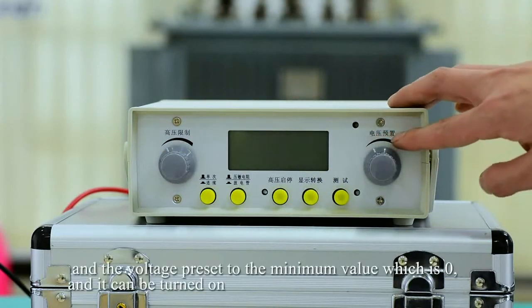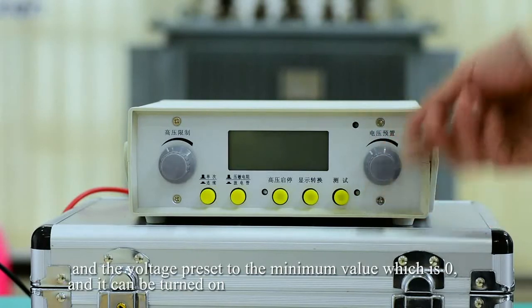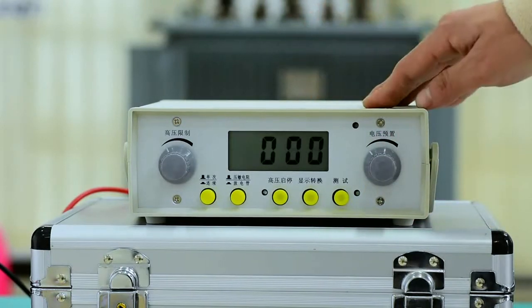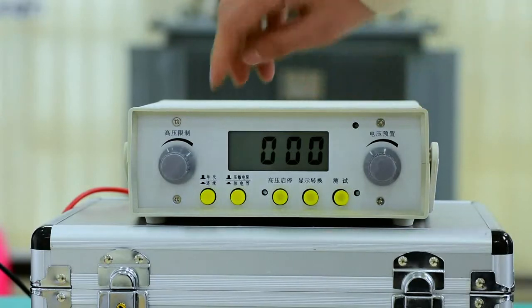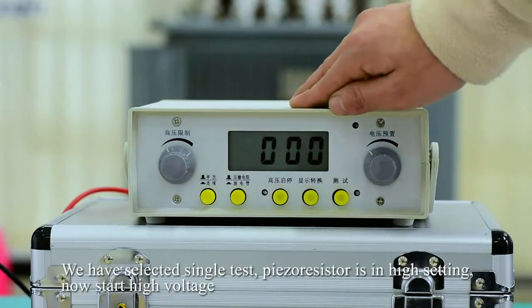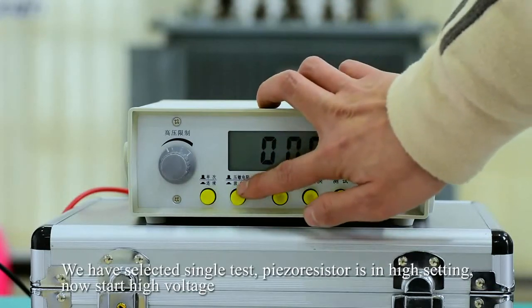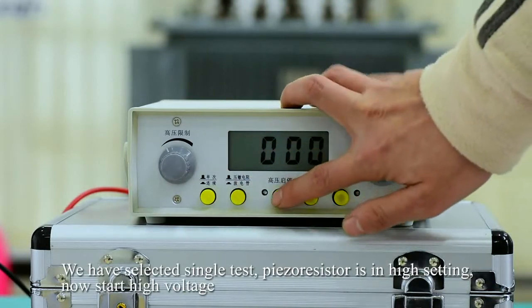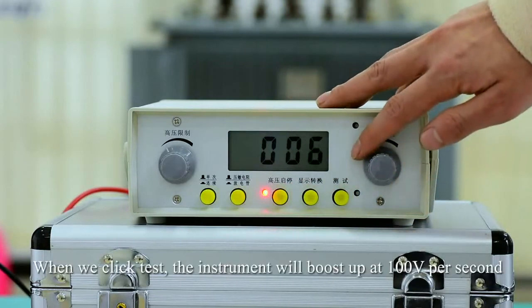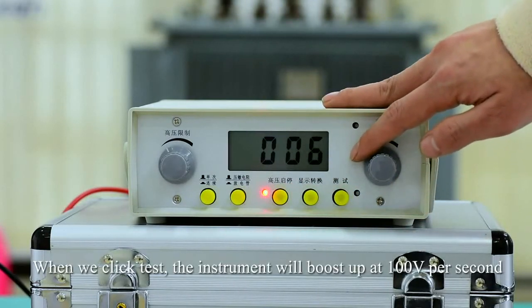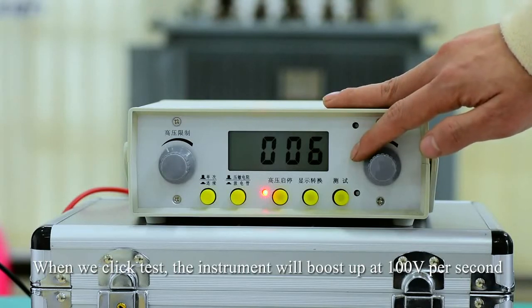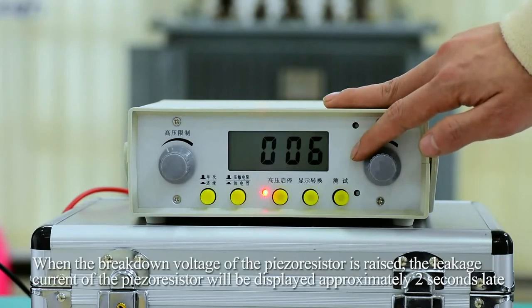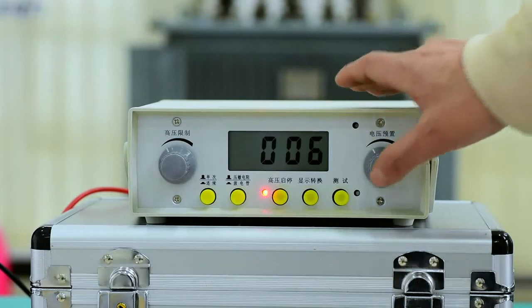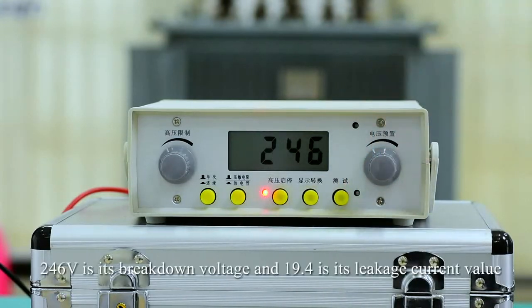And the voltage preset to the minimum value, which is 0, and it can be turned on. We have selected single test. The piezoresistor is in the high setting. Now start high voltage. When we click test, the instrument will boost up at 100 volts per second. When the breakdown voltage of the resistor is reached, the leakage current of the resistor will be displayed approximately 2 seconds later. Now let's click test.